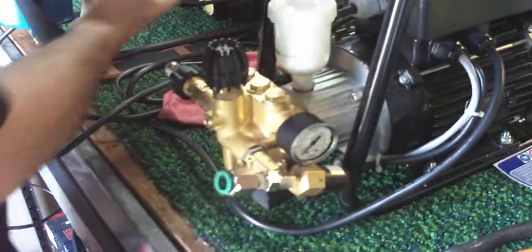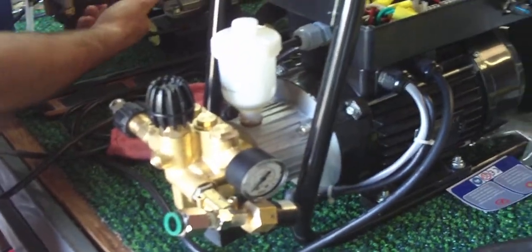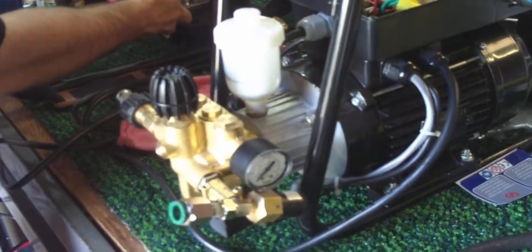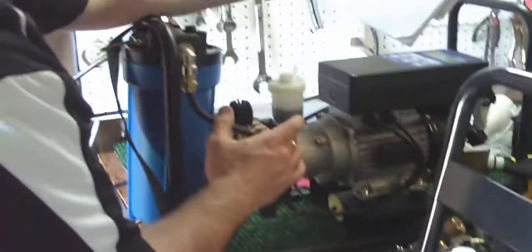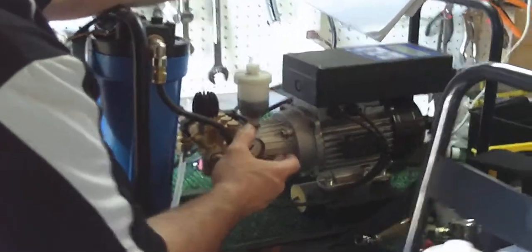As I mentioned before, water seals are only going to need to be replaced if this particular part of the pump is dripping water. That's the only reason you need to change the water seals.